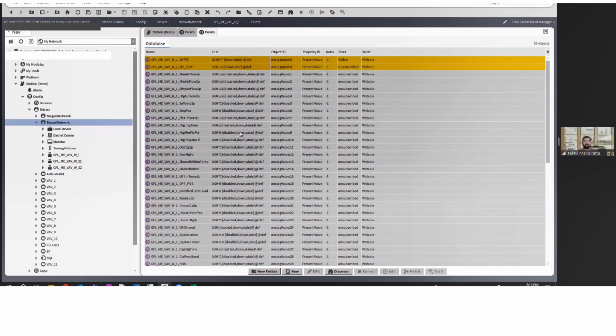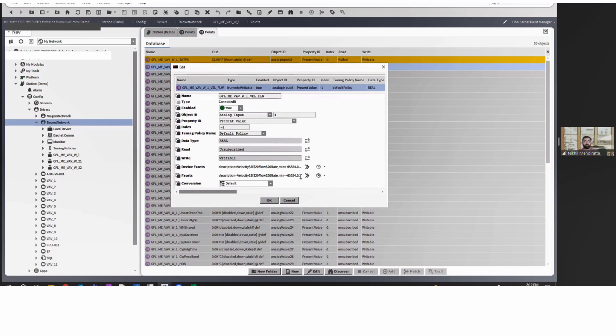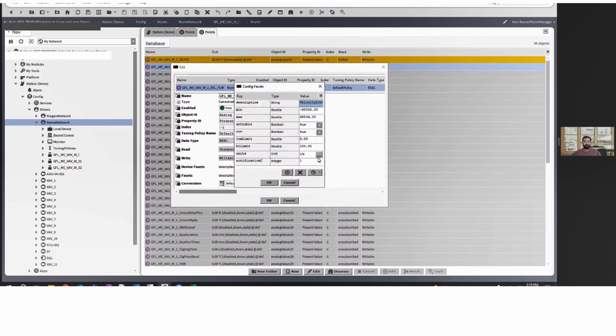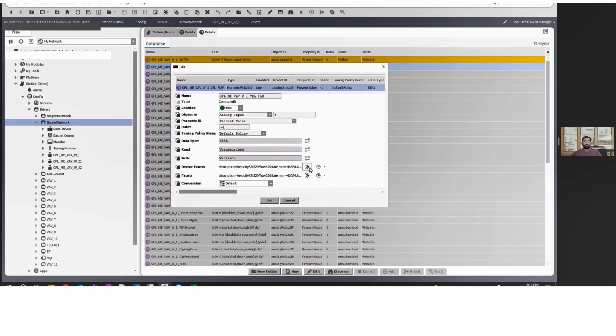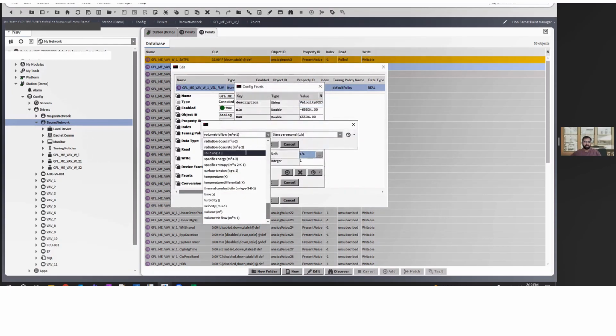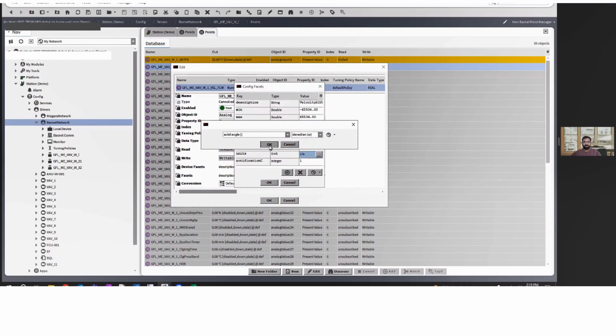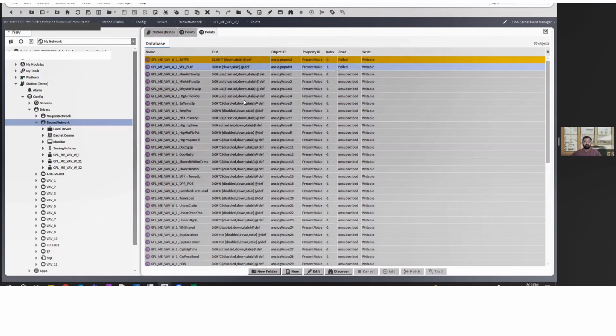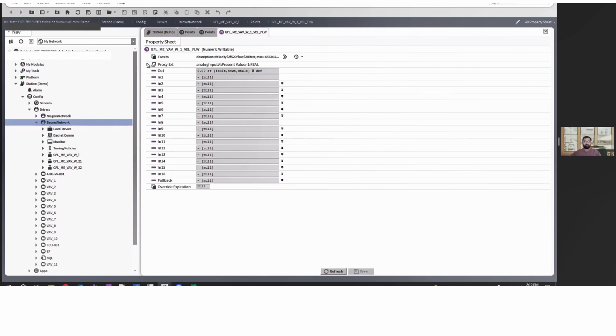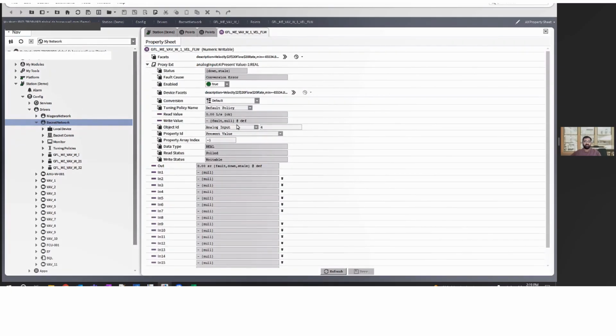Another good thing about Niagara: let's take this example, velocity flow. Here the facet is liter per second. However, if a user made a mistake and instead of liter per second changed it to, say, solid angle and steradian, and I hit OK, it will straight away go into fault. If I go to the property sheet and proxy extension, it will give a fault cause as conversion error. That's another advantage of Niagara—it tells you in real time that you've made a mistake in using the facets and units.